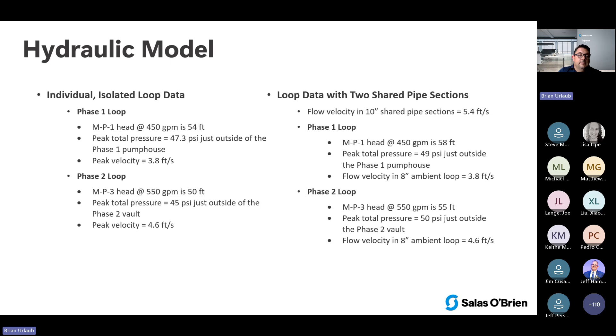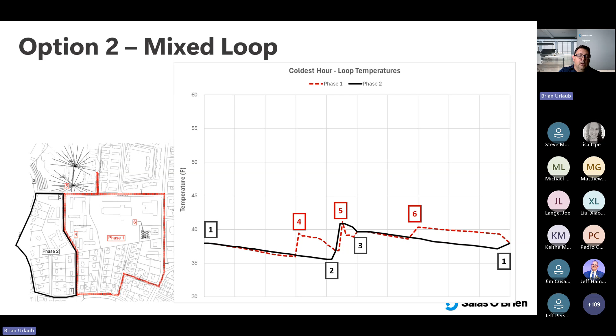If we show how these two mix together now, you'll notice on that other graph we had a difference of a few degrees between the two loops. Now you can see at each point where they mixed, loops 3 and 1, right here and right here, we actually flatline the two together, meaning they 100% mix to the same temperature. Once they go back out into their respective loops, they start changing temperature again based on the energy profiles of those loops. But those two 20-foot sections bring both temperatures to the same temperature, so we only needed 20 feet of 10-inch pipe to make that happen. That was a really interesting learning experience throughout this project.